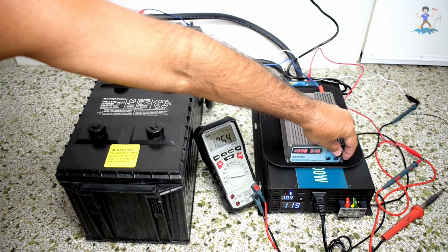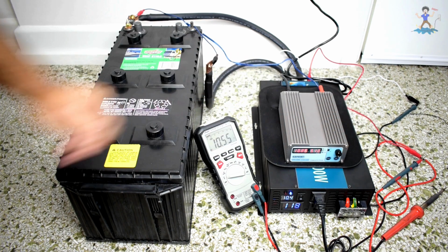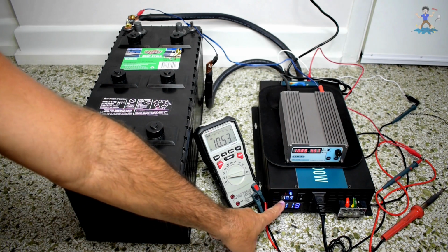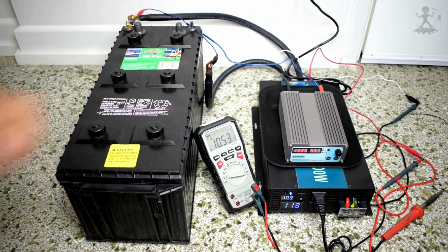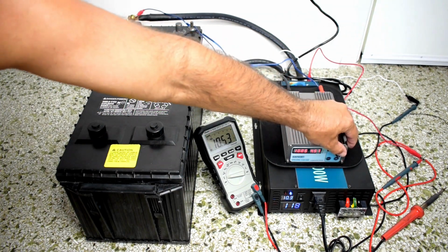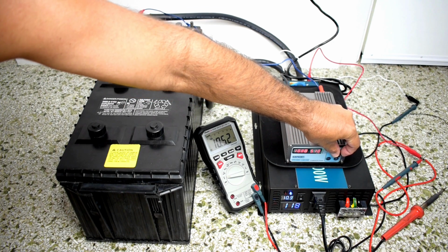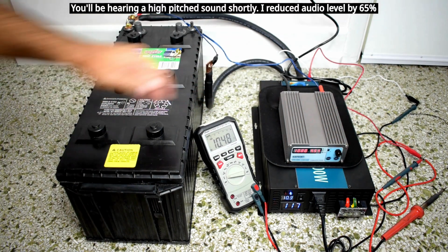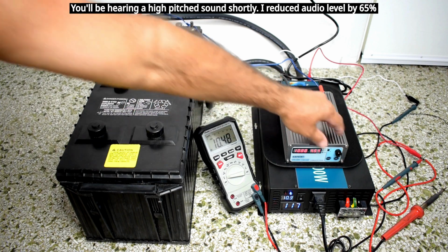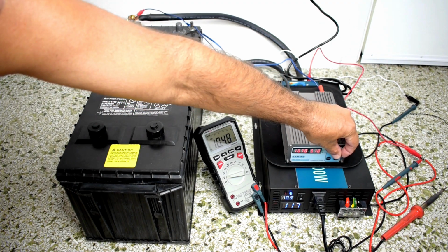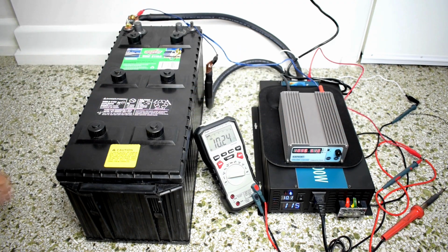Let's go to 10.85. Getting very close to the 10 volt range. A little bit more. 10.48. There you go, low voltage alarm.